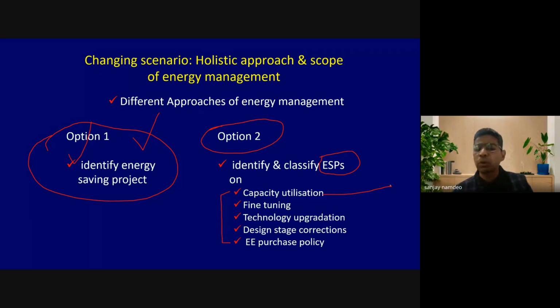For example, starting with the production capacity of the plant, what is the rated output of my plant, and how much is my present production? Similarly, what is the rated capacity of my chiller, and what is the actual utilization? This practice or study can be replicated to the entire plant and all equipment. So the first thing is they should know their capacity utilization factor. Then the second aspect is they should focus on fine tuning various parameters, for example time, temperature, pressure, batch time, batch operation, voltage losses, maybe power factor, etc. There are so many parameters.